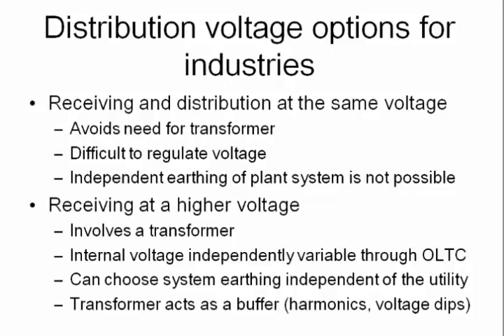So you might have just a direct low voltage supply from the utility, which saves you costs on the transformer. However, there is a downside. Lower the voltage, higher the current, higher the losses, poorer the voltage regulation. And in terms of your independent earthing, it's not easy. You can still have earthing, but you are interrelated with the utility earthing.